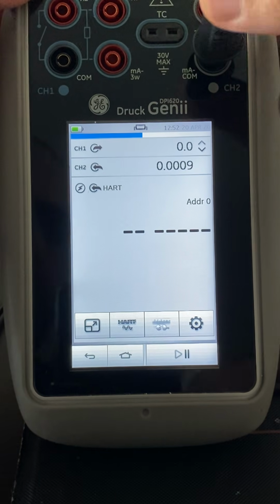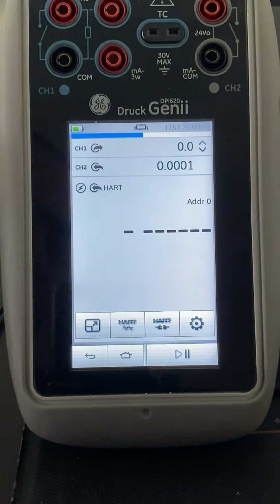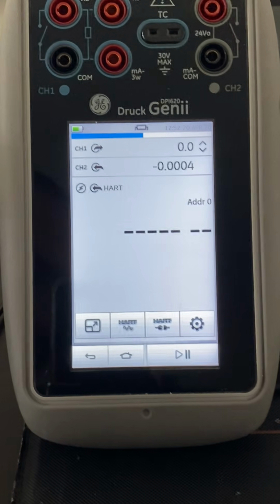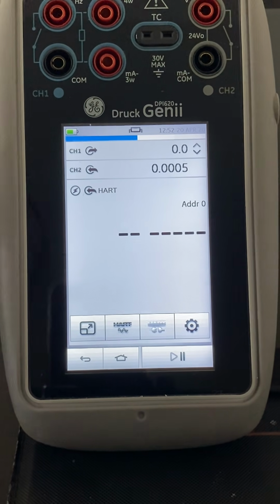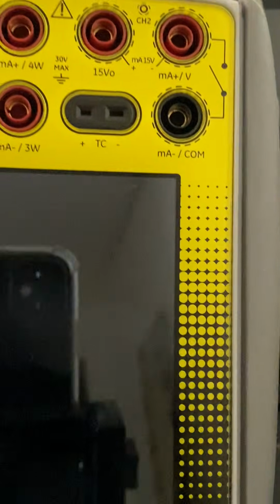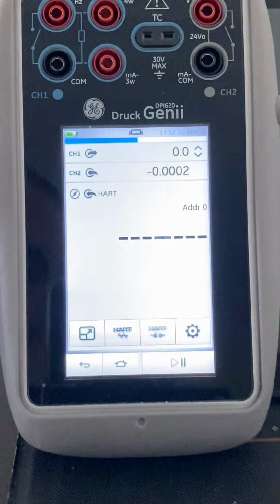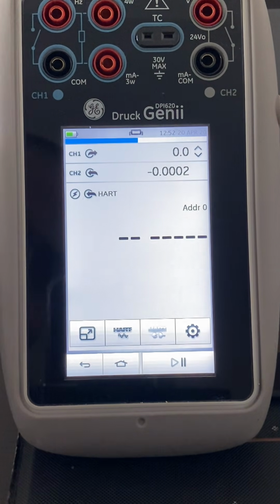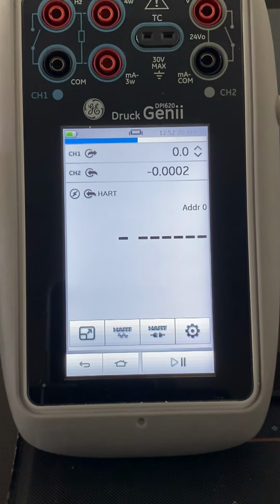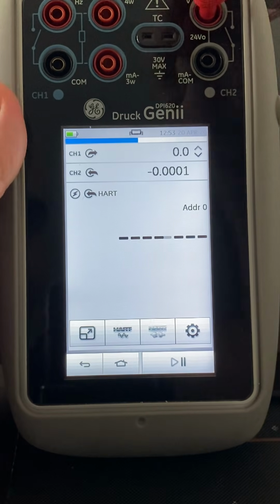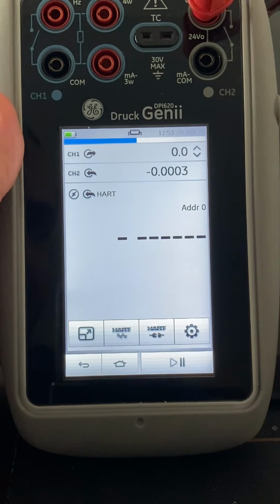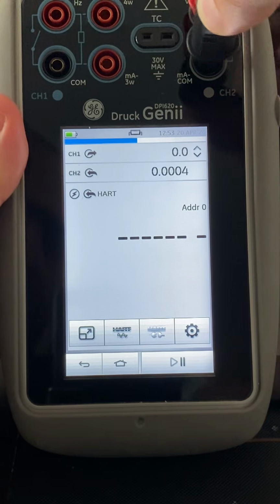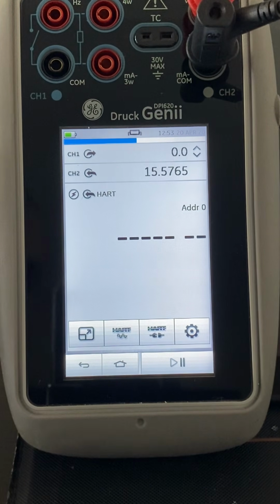In the DPI 620 Genii, channel 2 is the right channel to do the HART communication. It's different in the DPI 620 Genii IS because of the third port here. We have different configurations, depending on the condition we connect to. So I will have a separate video on how to connect HART on Genii IS. Let's connect our device to channel 2 now. The power supply is inside, the HART resistor is inside. What I have to do is just connect my device, and the communicator is also inside.